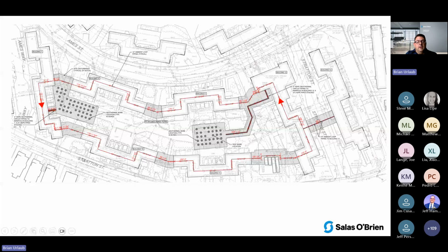Looking at the system, we have 7 buildings, and we're kind of limited on where we can connect our bore fields, and which direction to flow the water to make sure we're somewhat balanced. Also, do we want a hybrid system here? Initially I think we started out at 80 boreholes, and we were going to put some boilers in, then we dropped it to like 70, maybe 70 to 72 boreholes. Then working with the building team, they had goals of reaching 20 BTUs per square foot on a peak heating basis.